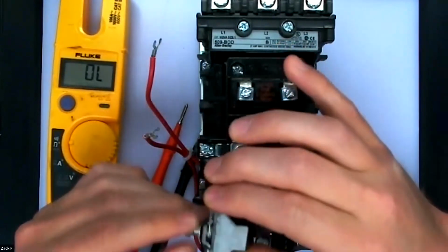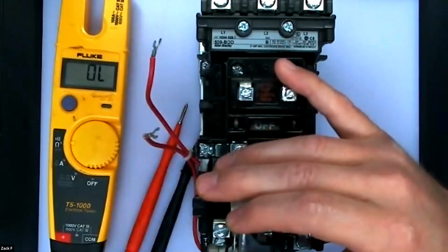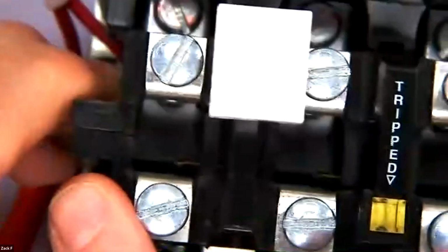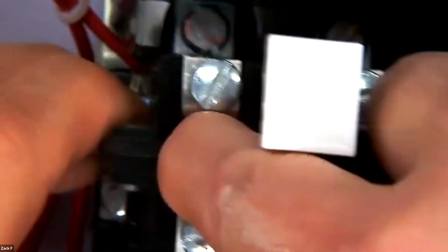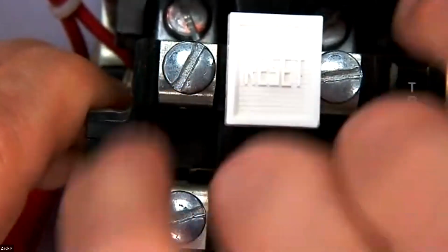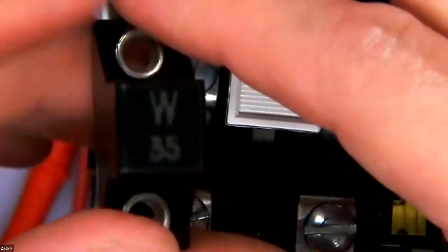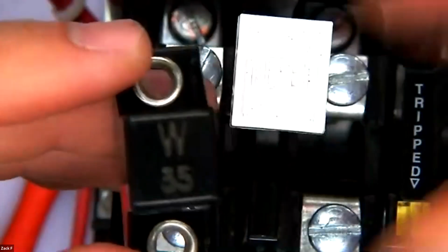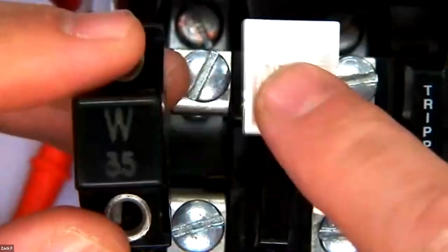This is a little spring. You can see that in there. So this is an overload heater. This spring becomes under tension when it heats up. It will unwind itself and trip. You can see inside there's a little bitty tab. When that trips, it breaks contact between these two points. Its job is to protect the motor windings, right? If this gets too hot, it's saying, hey, this motor is getting overloaded, we need to open up. And if it trips, this reset button will reset it.